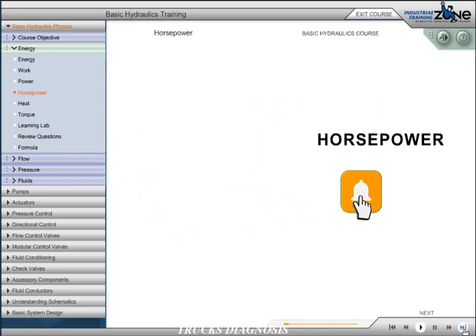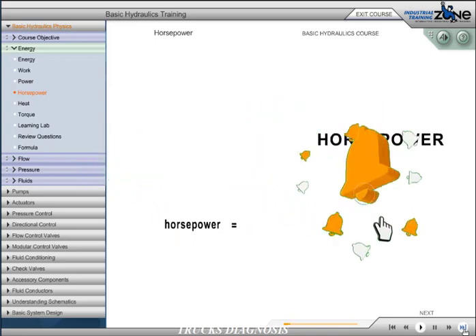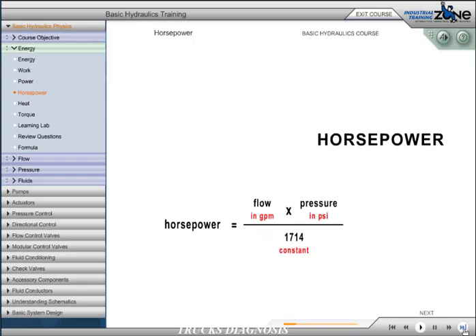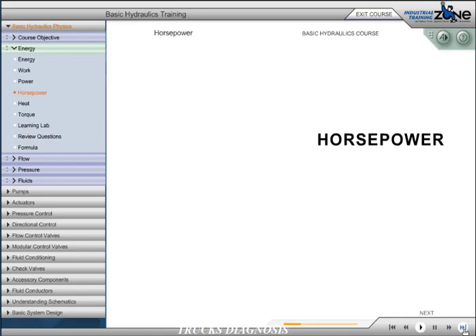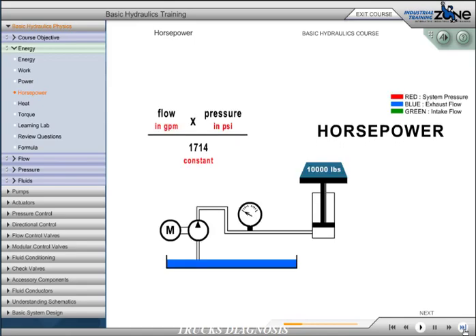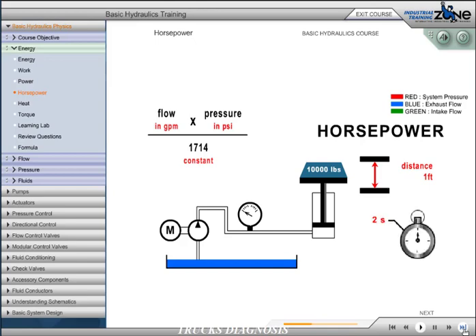Mathematically, hydraulic horsepower is expressed as follows. Horsepower equals flow in gallons per minute times pressure in pounds per square inch divided by 1,714, a constant. In our illustration, we are lifting 10,000 pounds, this is our force, a distance of 1 foot. This is the work to be accomplished. If we lift our load in 2 seconds, we have defined a power requirement. This may be expressed as hydraulic horsepower.